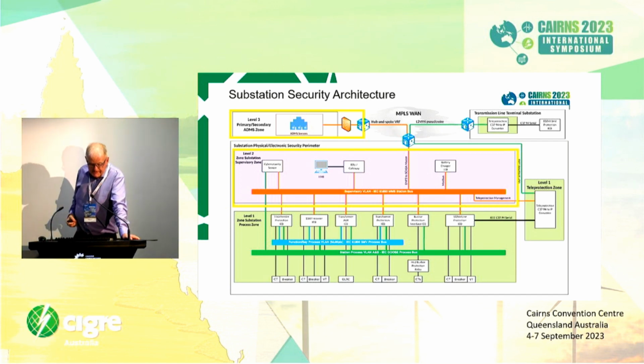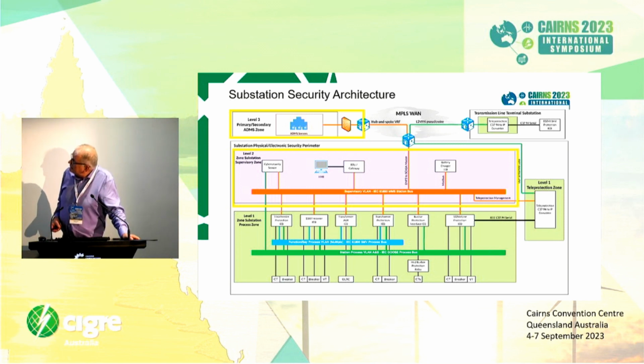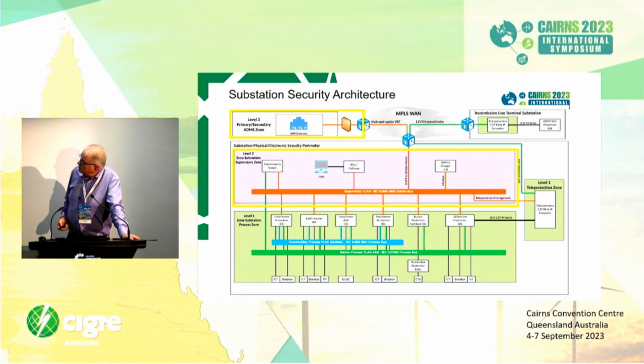We've got our SCADA master station up the top there, the ADMS zone. It talks out via the MPLS network. We've implemented a hub and spoke configuration where all the substations are on a spoked network. They all point back to the SCADA master station as the hub, and that really enables us to bring the firewall back to the hub of the network, so we don't have to deploy firewalls at each substation. Substations are actually protected centrally, back at that master station central site.